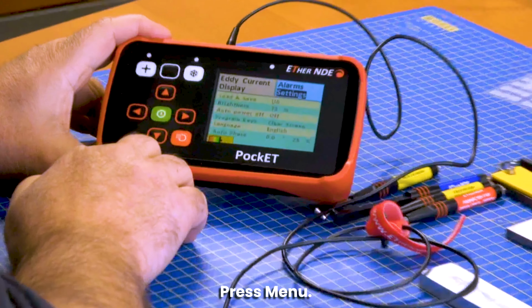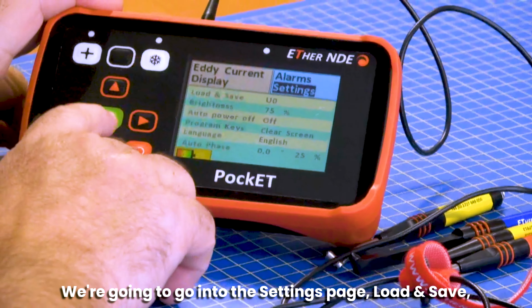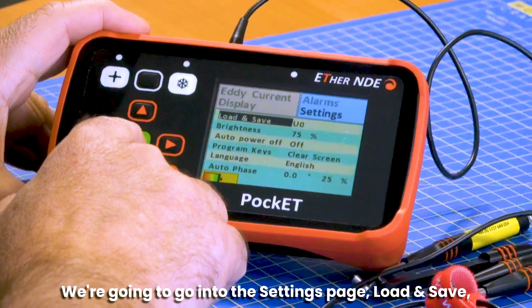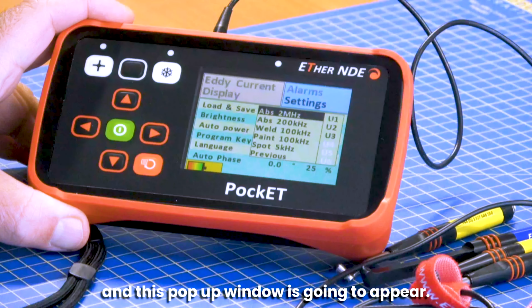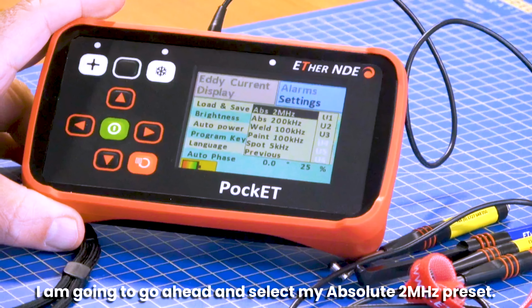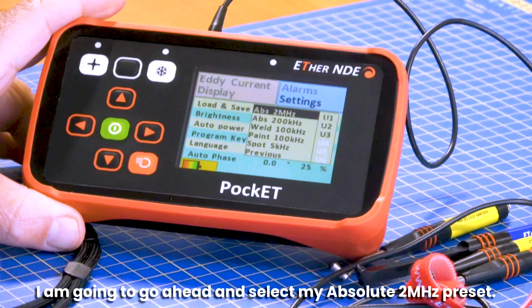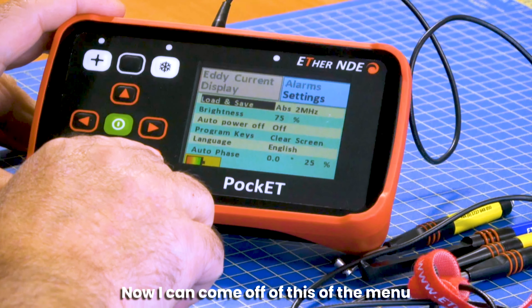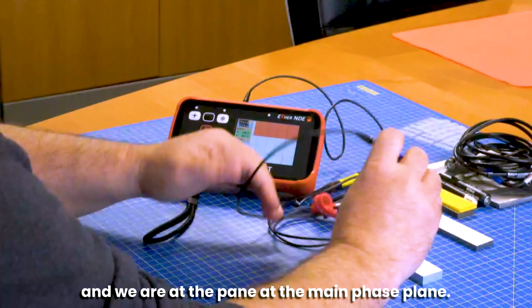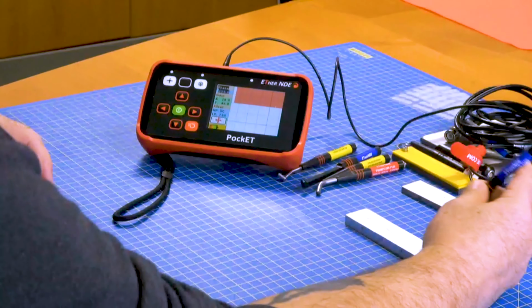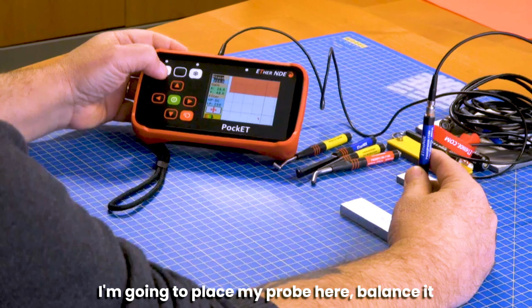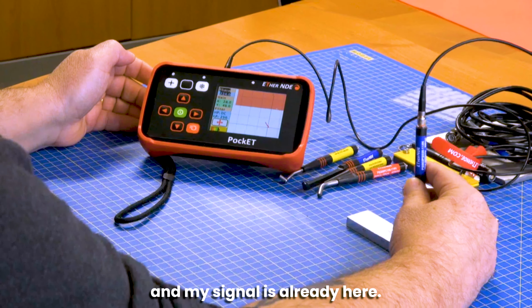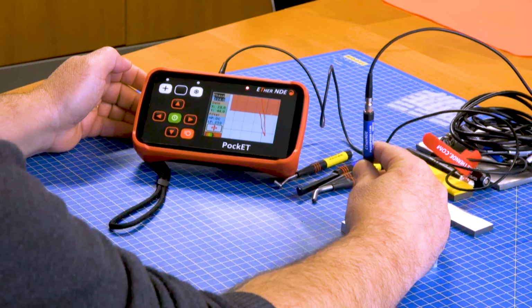With this connected, now I go into the instrument, press menu, we're going to go into the settings page, load and save, and this pop-up window is going to appear. I am going to go ahead and select my absolute 2 megahertz preset. It has been loaded. Now I can come off of the menu and we are at the main phase plane. I'm going to place my probe here, balance it, and my signal is already here.